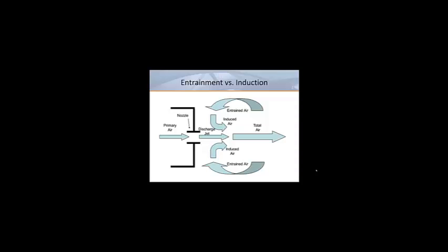Before we continue, we need to understand the difference between the terms entrainment and induction. These two terms are often used interchangeably in our industry, but they don't have the same meaning, and induction is very important to the operation of an active beam. When air discharges from an outlet, room air moves towards the outlet resulting in low-velocity room air motion. This is called entrainment. Some portion of the air involved in the low-velocity room air motion actually reaches the outlet and mixes with the discharged jet. This is what we refer to as induction.